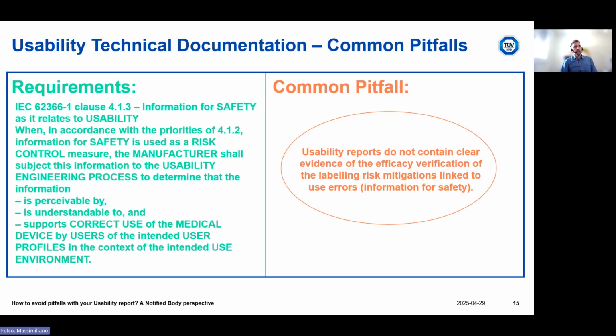So, in general, identifying a labeling element as a risk control measure is not enough. The manufacturer has to validate the efficacy of the risk mitigation put in place by the labeling element in the usability evaluation, for example, during the summative phase. The common pitfall is that usability reports do not contain clear evidence of the efficacy verification of the labeling risk mitigations linked to use errors. Of course, it is all related to the use and to the use errors for the medical device under development.